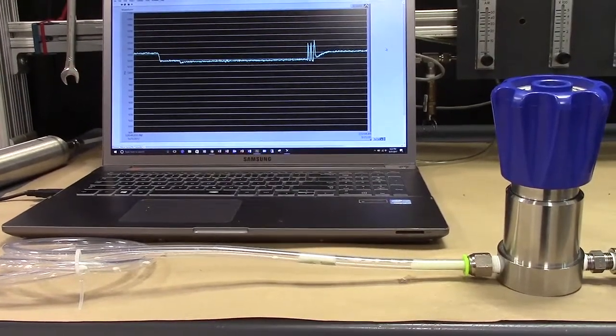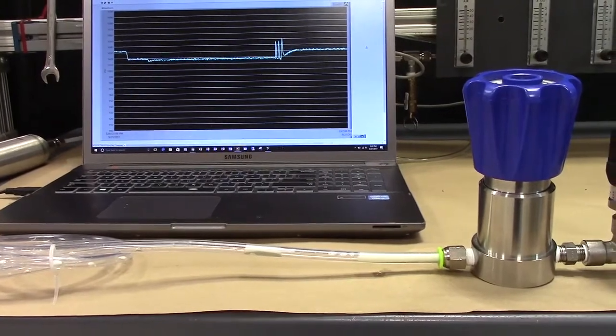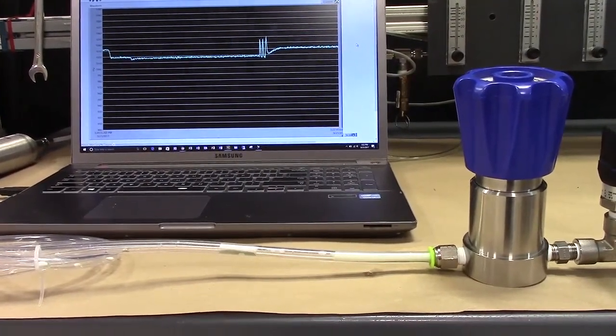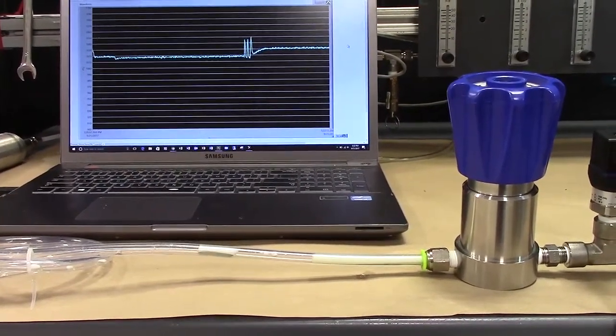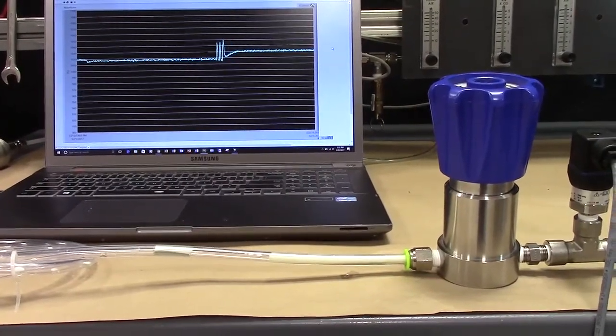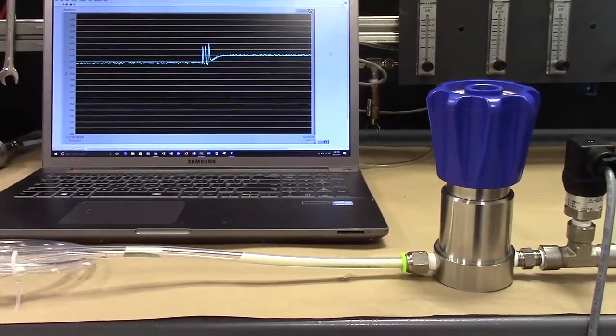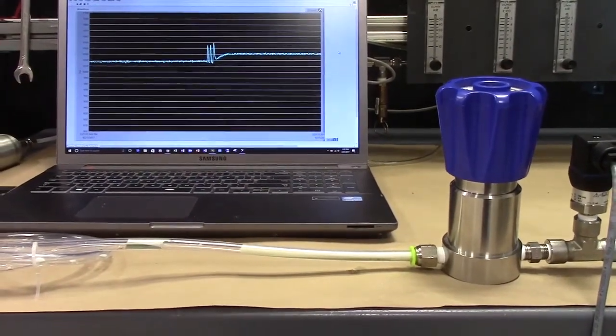As the flow evolves we can see these slugs of liquid moving through and we see irreversible pressure gain on the order of about 10 psi per graduation of inlet pressure. So now we've gained 10 psi of inlet pressure and are slightly continuing to build as a result of the liquid moving through the regulator.